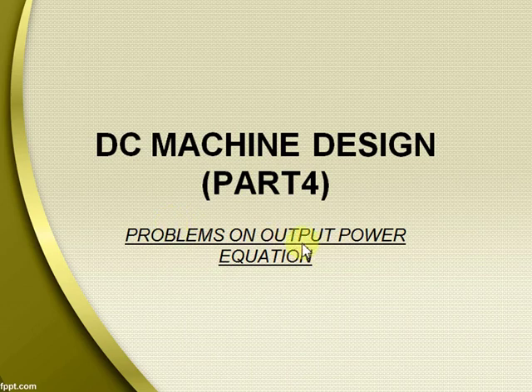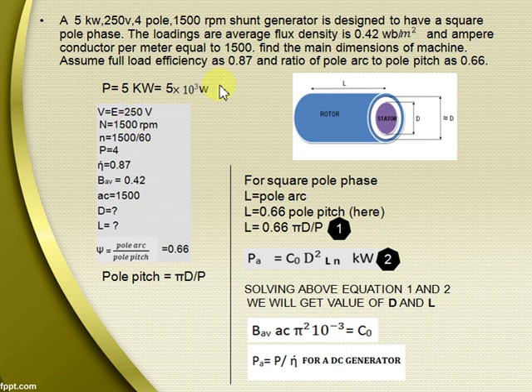Problems on Output Power Equation. A 5 kW, 250V, 4-pole, 1500 RPM shunt generator is designed to have a square pole phase. The loadings are average flux density is 0.42 Weber per meter square and ampere conductor per meter equal to 1500. Find the main dimensions of machine. Assume full load efficiency as 0.87 and ratio of pole arc to pole pitch as 0.66.